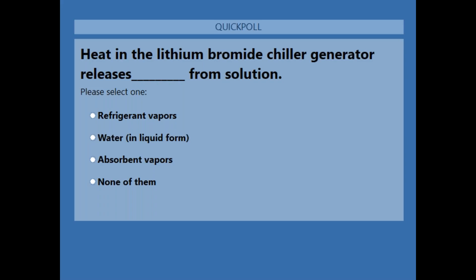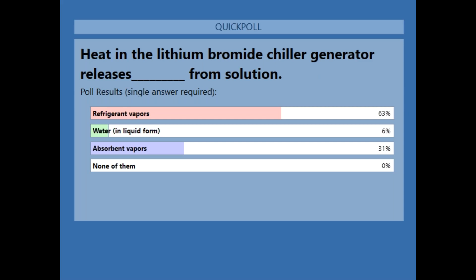63% of you are saying refrigerant vapors, and that is the right answer because the refrigerant here is water. In the generator, you heat the solution, separating the water from the lithium bromide, generating water vapor — that is the refrigerant vapor, in other words water vapor. It's not water in liquid form, which happens in the condenser, and it's not absorbent vapor either. Majority of you got the right answer.